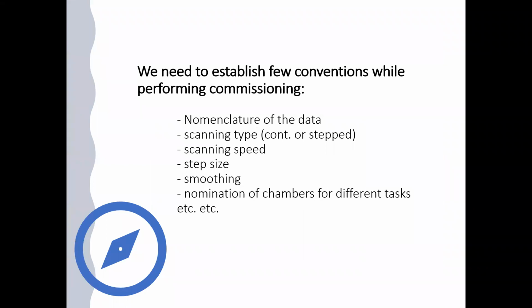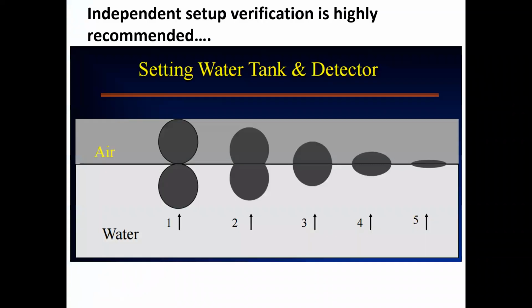A few things are required to establish while performing commissioning. We need to define the nomenclature of the data. What will be the names of the files in order to make things uniform? Scanning type: either we are going to perform all the dosimetry in continuous mode or step mode, keeping the scanning speed, step size, smoothing, etc. And it is highly recommended that someone should check the setup independently. This is highly recommended while starting your day for commissioning.